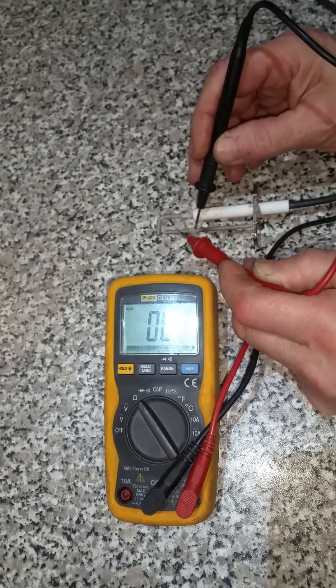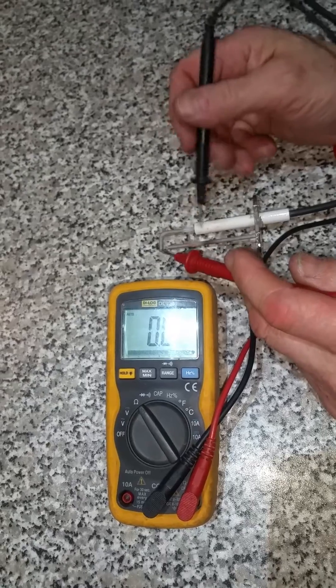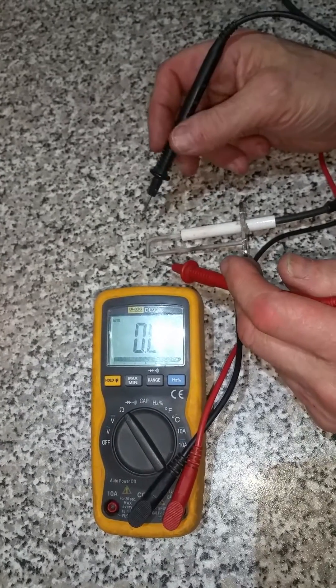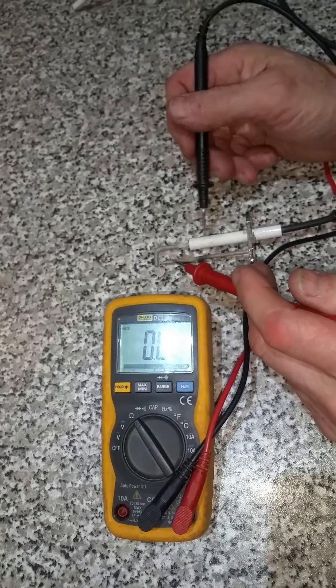With the conductivity — and to be honest, what happened was I went to the job, cleaned up this electrode, put it back in, and still had an explosive ignition. Then I remembered your video and what you said, pulled it back out, tested it, and found exactly what you described.